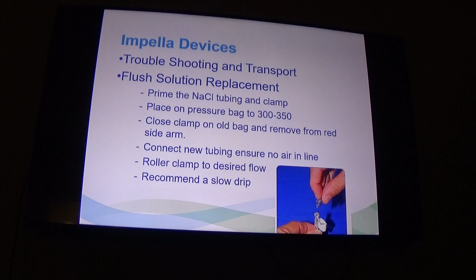There's the whole manual, and 99% of the time you're going to have either a rep or someone taking over the device. Most of the time they just swoop in and take over. I've only had one so far where we did it, and again, it's not very hard. You just basically do exactly what it says. Turn the monitor on, disconnect that major cable, put it into the new one. Hit OK to restart the prior settings.